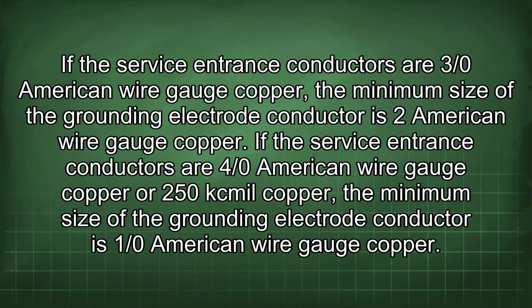If the service entrance conductors are 3/0 American wire gauge copper, the minimum size of the grounding electrode conductor is 2 American wire gauge copper. If the service entrance conductors are 4/0 American wire gauge copper or 250 kcmil copper, the minimum size of the grounding electrode conductor is 1/0 American wire gauge copper.